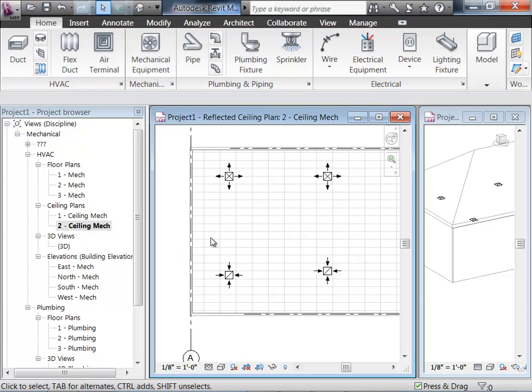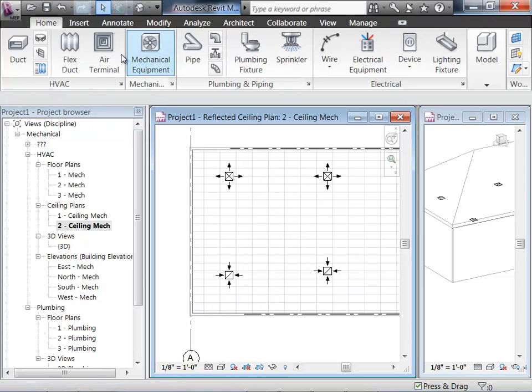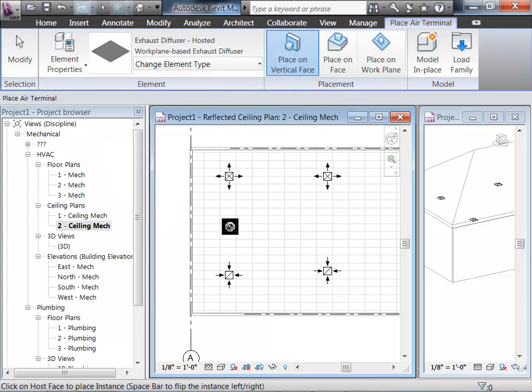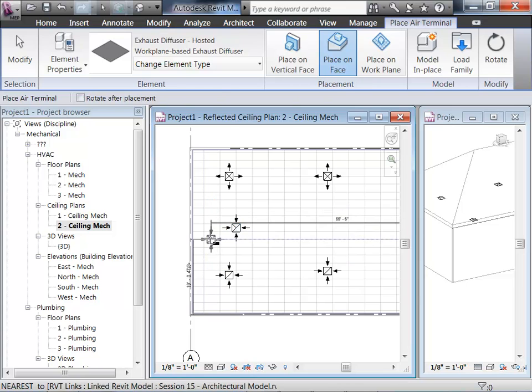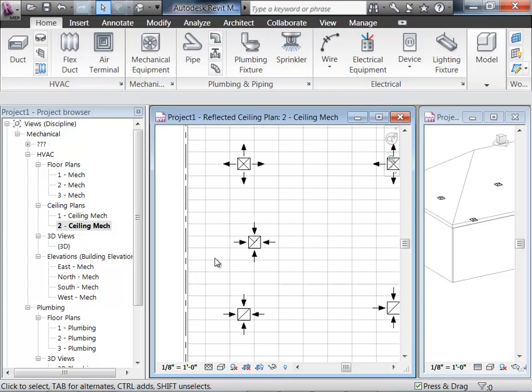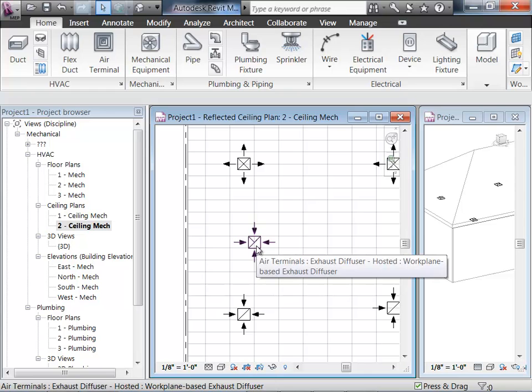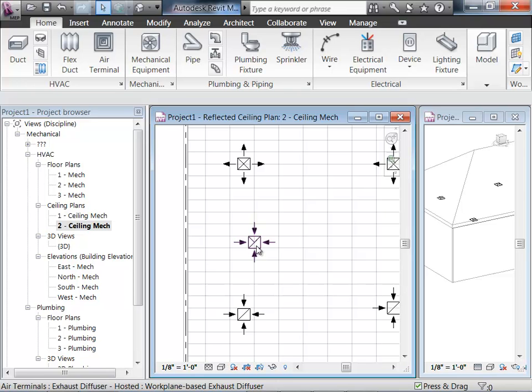Although I'm not going to place an exhaust grill here permanently, I'm going to quickly place it just to show you how the symbols look. These are typical annotation symbols for supply, return, and exhaust. Supply has an X in it; return has just one diagonal line; exhaust has a diagonal line and a half diagonal line. That's standard, but you should always check the symbols sheet on a drawing set to verify.